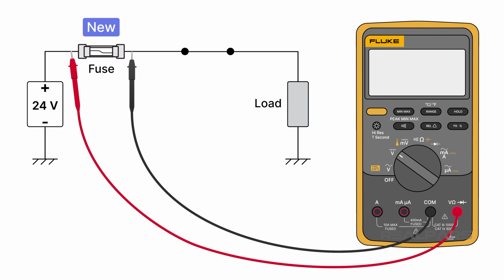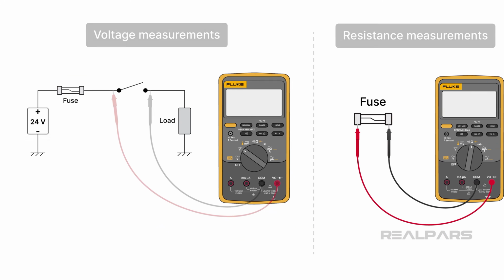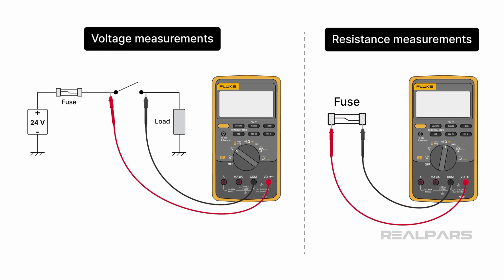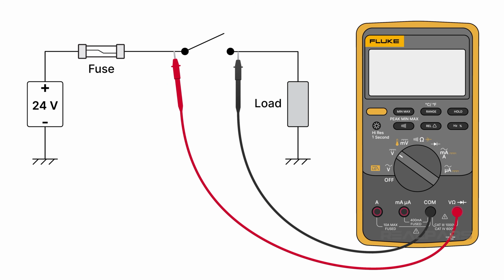Measuring voltages across every component works, but it isn't very efficient and often confusing. I'll get to a more efficient troubleshooting method shortly. Principle 4. Voltage measurements are usually better than resistance measurements. While live testing voltage measurements are easier to perform and often eliminate the need for resistance measurements, they must only be performed under safe, controlled conditions.